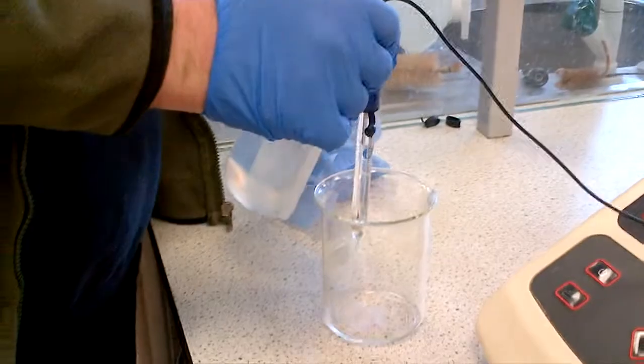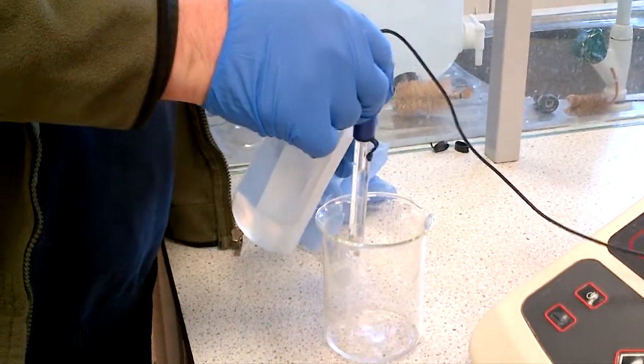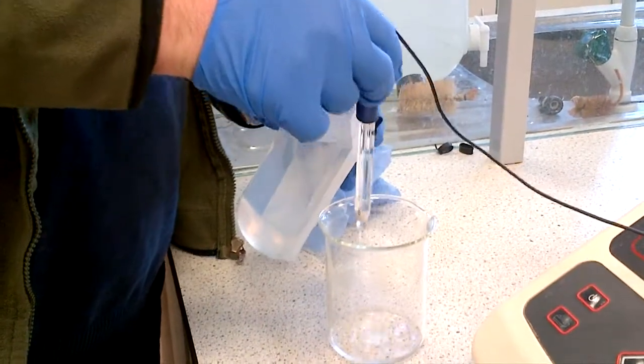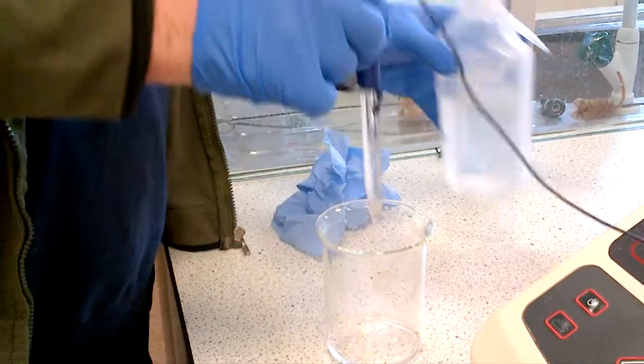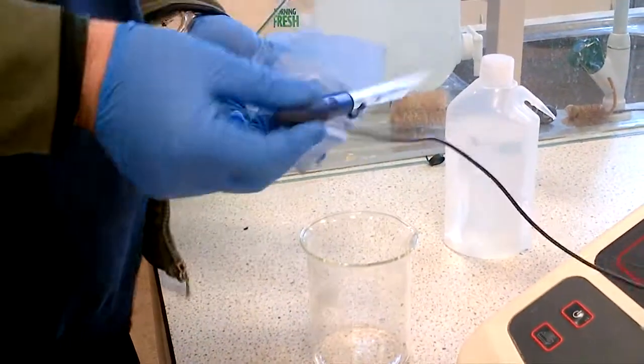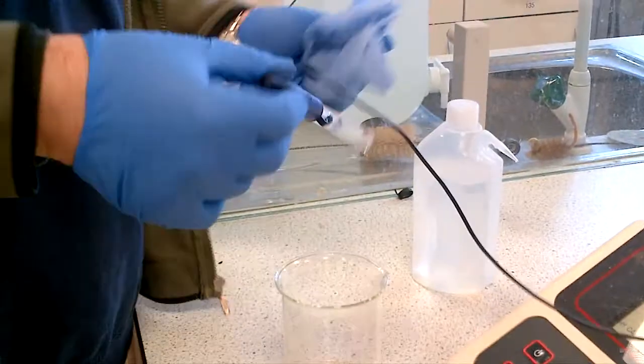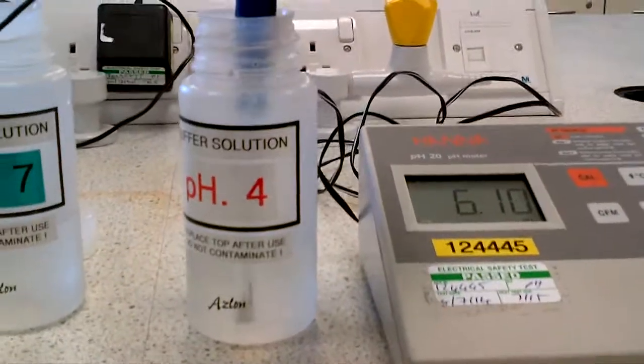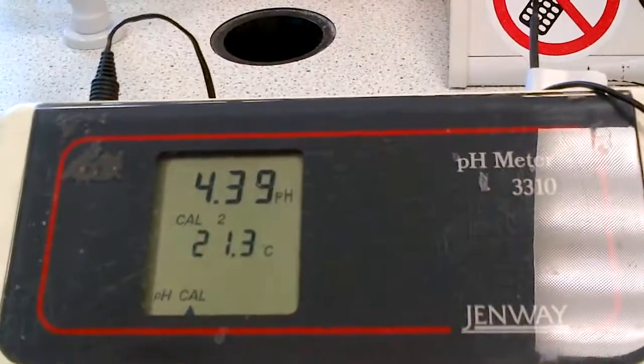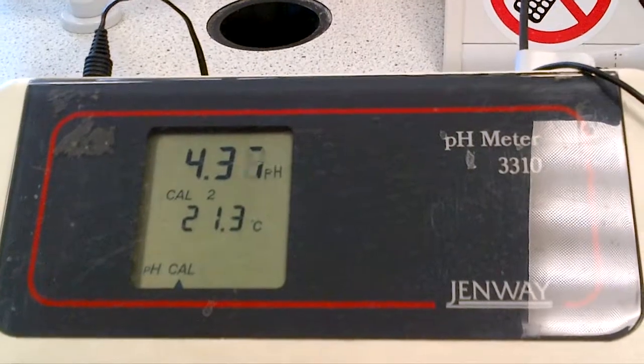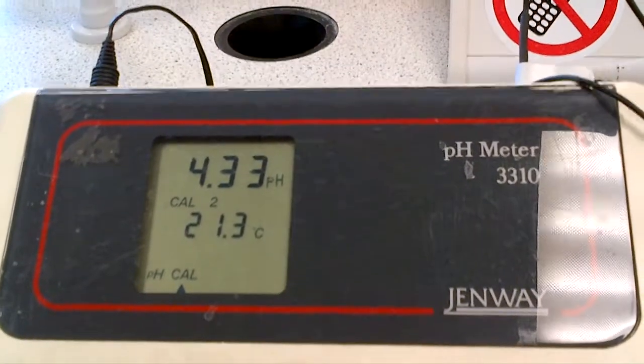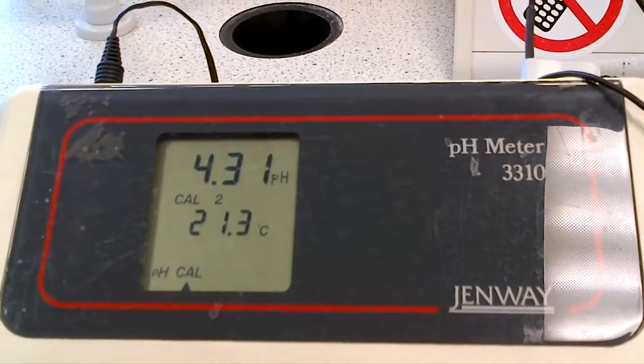So we take it out and wash again with distilled water. Make sure the electrode is rinsed thoroughly. Shake, dry again with tissue paper perhaps, and then we'll go into the next buffer. Let's go for 4 and place it in there. We note that we've got a 4.39 reading, so we'll give it a second just to make sure we get to the correct level, and we'll move down.